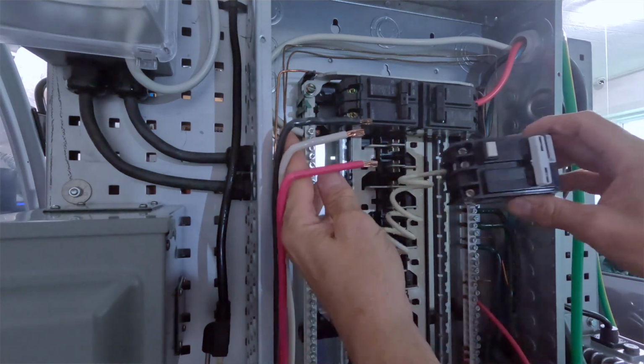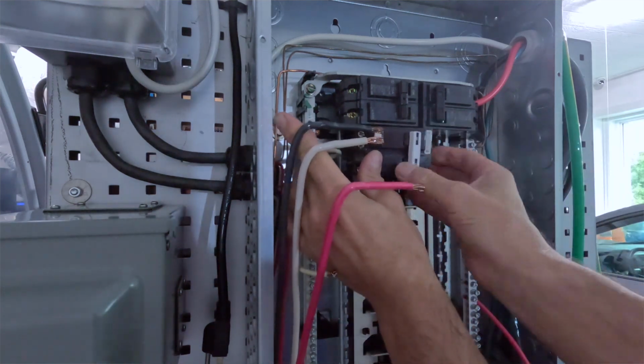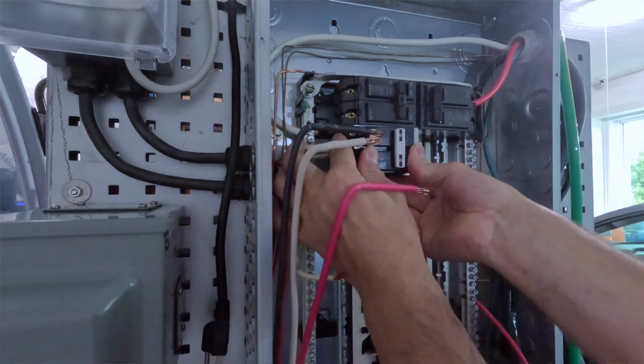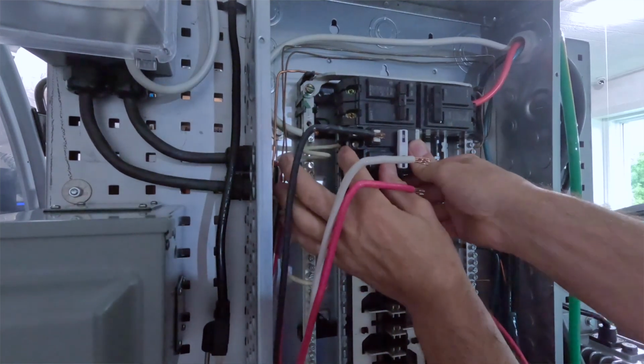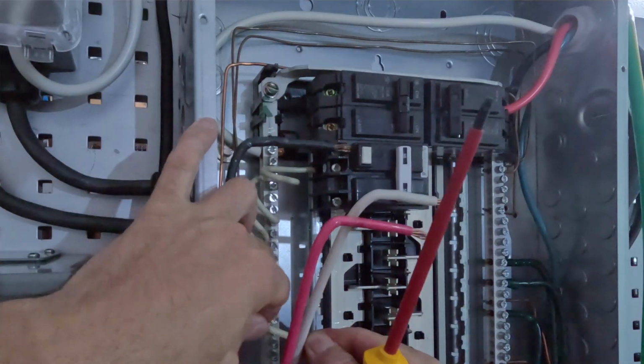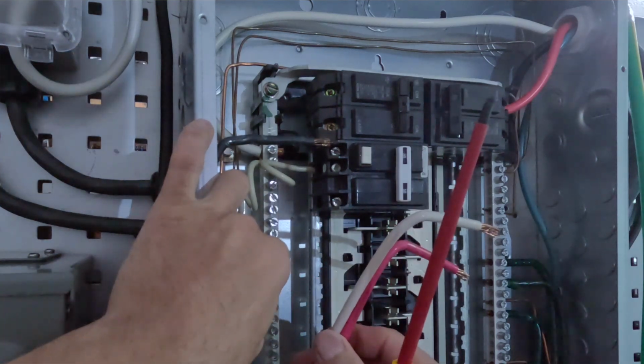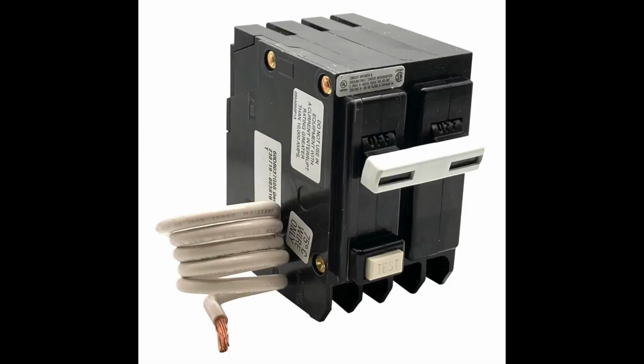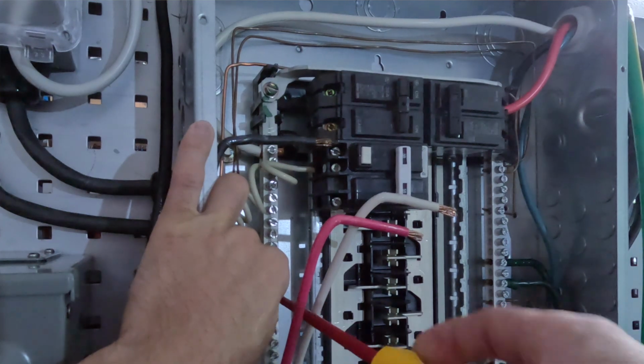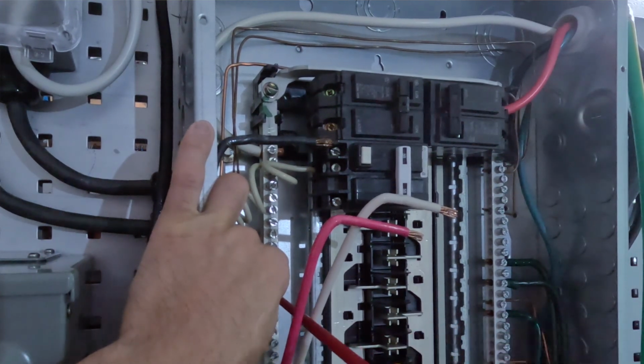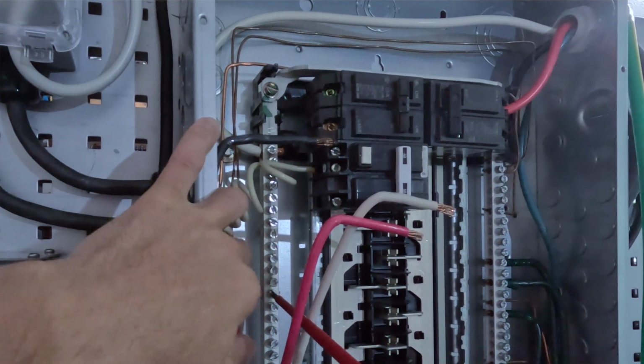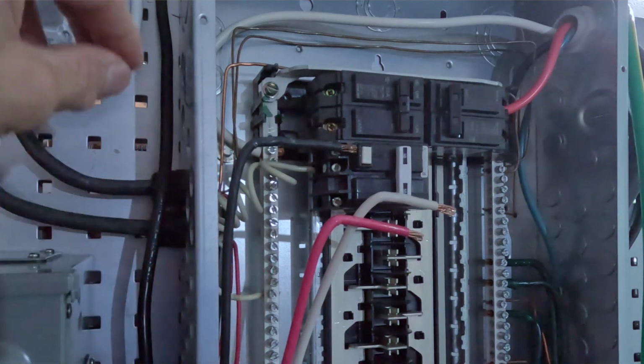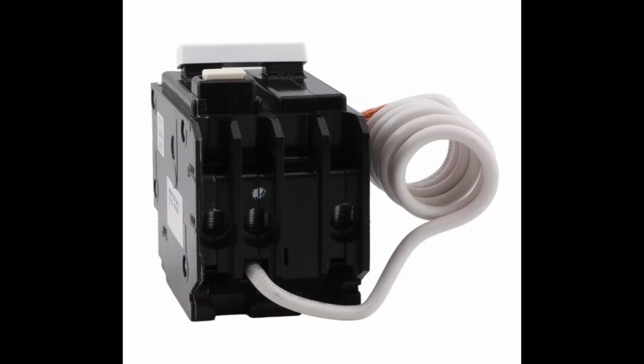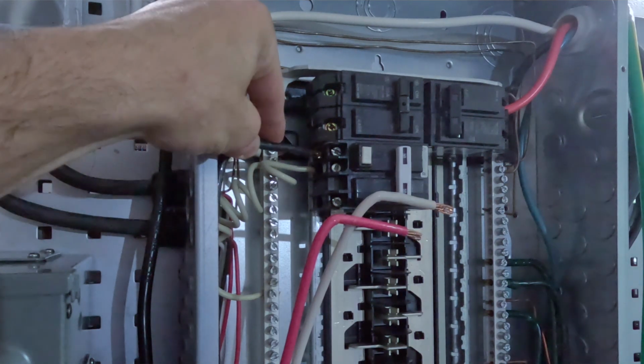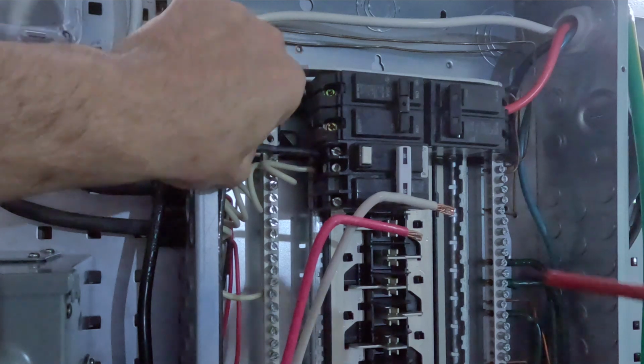We are going to connect the receptacle to a 50 amp GFCI double pole circuit breaker. The main difference between this breaker and the one without GFCI is the extra wire that is attached to the breaker, and the test button. When we connect this type of breaker to a panel, the attached neutral wire connects to the neutral bus bar. And if you look at this picture, there is an extra connection point above the white wire. This is where we're gonna connect our neutral wire coming from the receptacle.